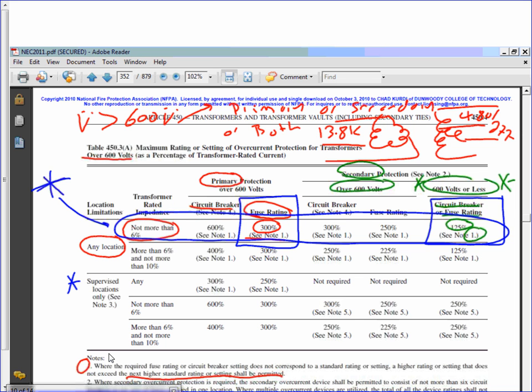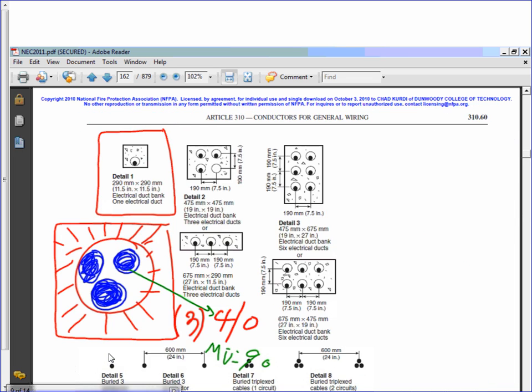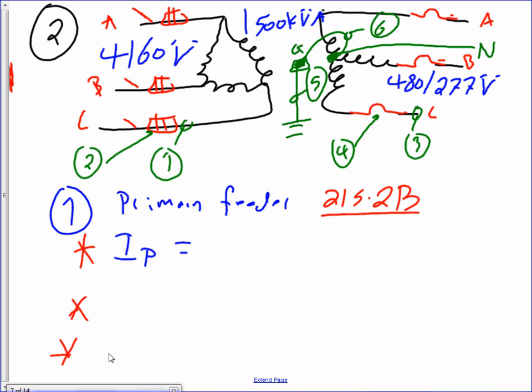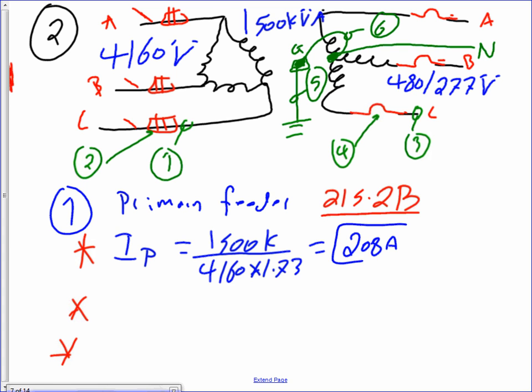Any comments, any questions, guys, about this table? So that's to size your fuses. So let's go ahead and size the conductor first. We'll do that when it comes to the fuses. All right, so how do you size this? We've got your transformer. Here's my 1500 kVA. Divide this one by 4160 times 1.73. When you go there, that will get you a healthy 208 amps. Very easy, straightforward.